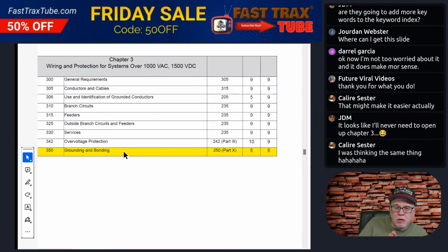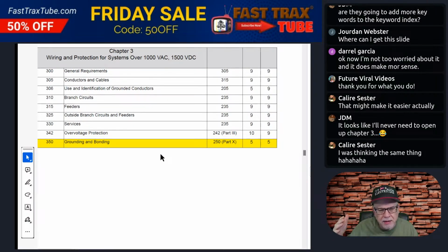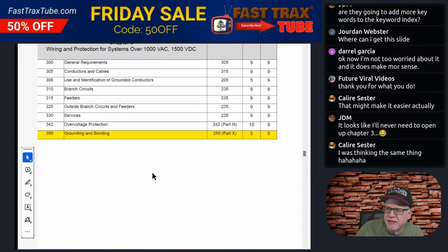And grounding and bonding, right? Instead of having it intermingled with what you and I are used to doing for normal grounding and bonding, why not move those things into 350 and put it with the over 1,000 volt? Makes sense. Instead of it being in a part, like part 10 of 250, let's give it its own article within chapter 3. That way, everything in here is nice and tidy for these over 1,000 volts, so that when we have something else we need to add that's over 1,000 volts, systems for wiring and protection, it goes right here. It's no longer piecemeal, it has a place. Now, I'm not naive enough to say this won't expand, but once you set the foundation down and lay it out properly, it's going to be much easier to put things where they need to be.